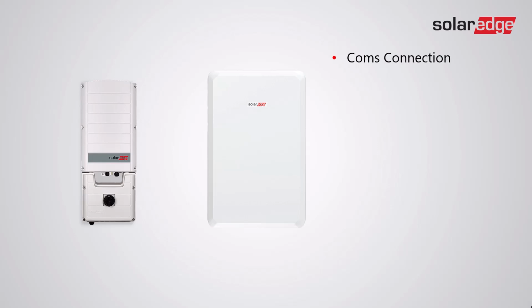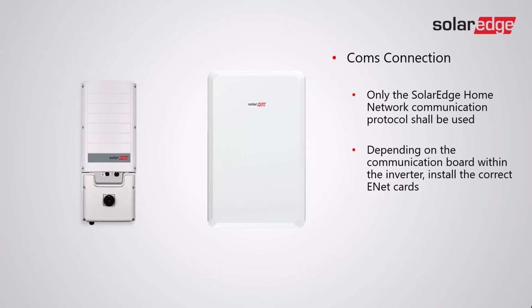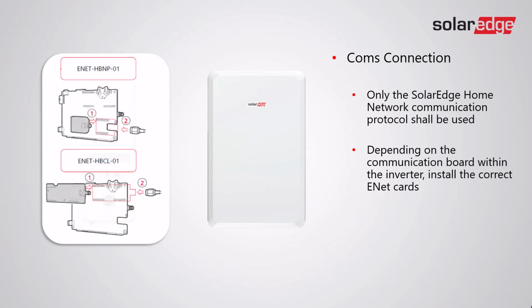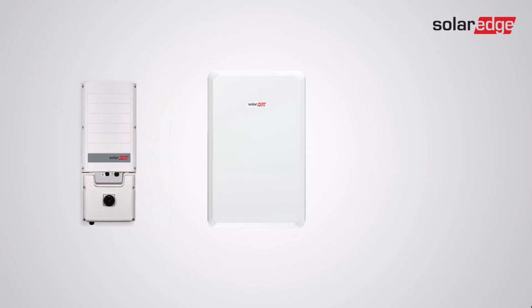For the comms connection, only the SolarEdge home network communication protocol shall be used. Depending on the communication board within the inverter, install the correct EnergyNet card. There are two types of EnergyNet card, the HBNP-01 and the HBCL-01. The HBCL-01 is the larger EnergyNet card that needs to be installed on communication boards that do not have the smaller connection port. On boards which do have the smaller connection port, ensure that the HBNP-01 is used only.